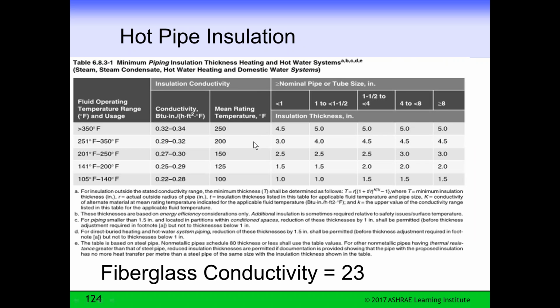Hot pipe insulation is similar. It has the same requirements and is based on fiberglass, but we have more breakdown from 105 to 140 all the way up to above 350. We have different requirements, and obviously as you get hotter and hotter, it pays off to have more and more insulation.